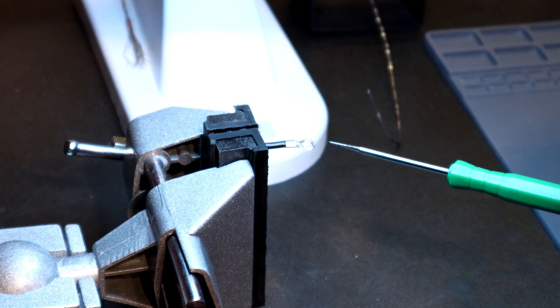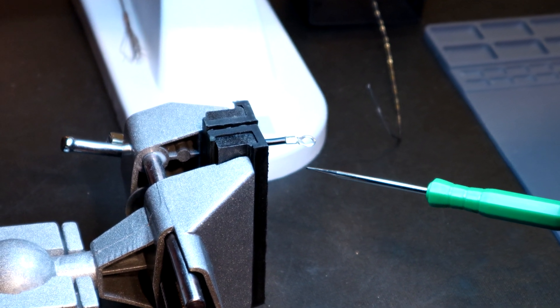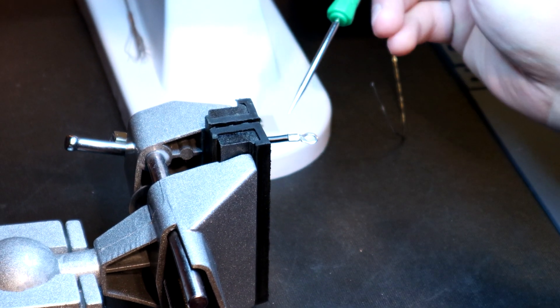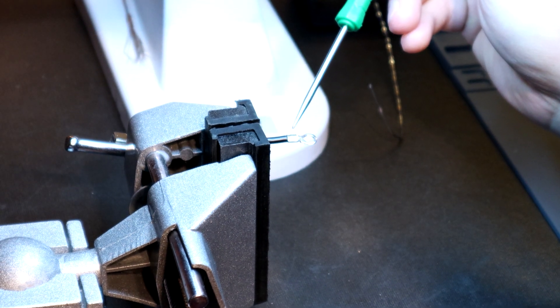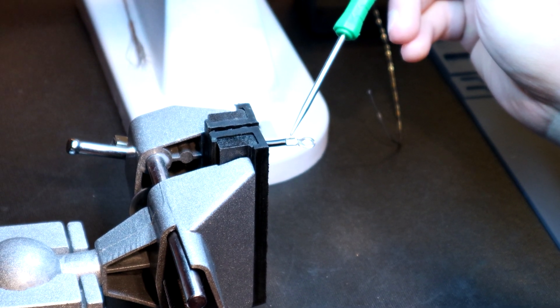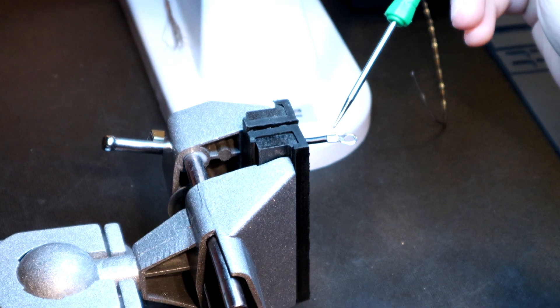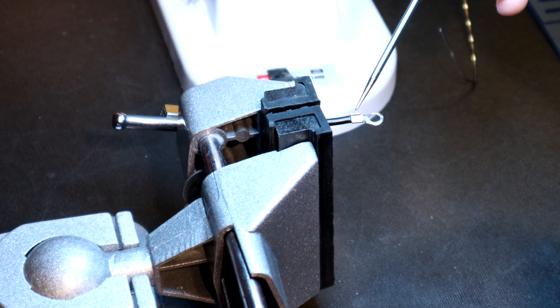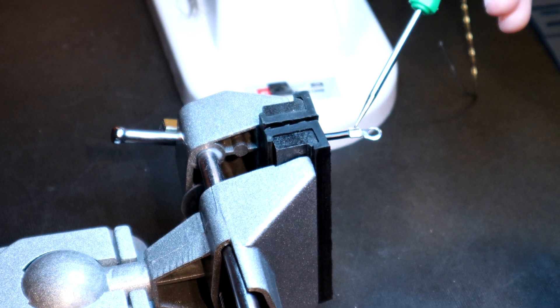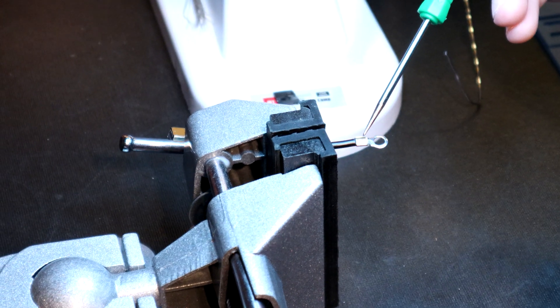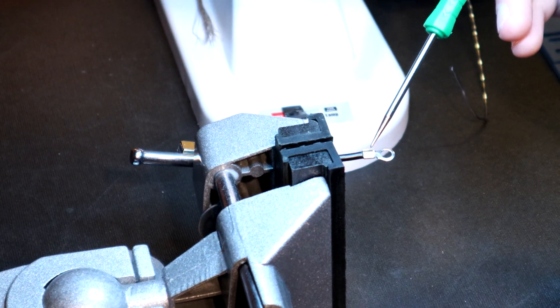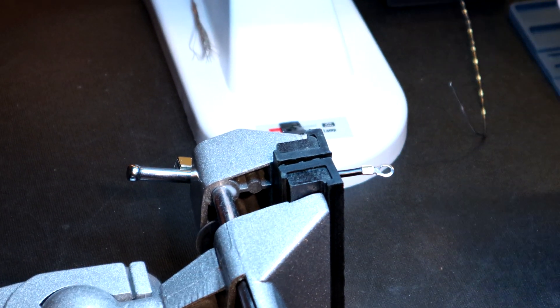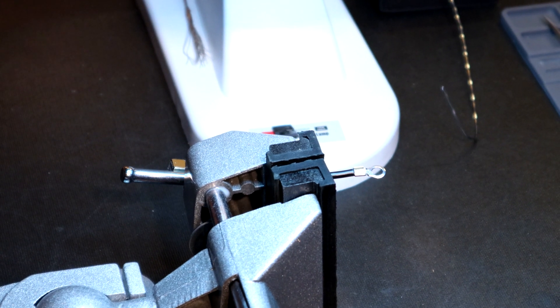There is no such thing as rushing if you're trying to get the job correctly done. We want full penetration with our solder. And what's going to happen is once we apply heat to the top of this conductor, we're going to apply the heat with the solder, and the solder through capillary action and heat will be sucked into where the flux is penetrated and made contact with the conductor formulating a bond. And that's the weld we're looking to get.